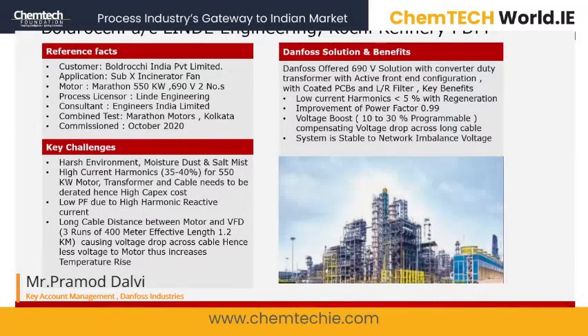We can program up to 30%. This will compensate the voltage drop across the cable. The motor will see the exact nameplate rated voltage, and there are no issues of lesser voltage and higher current and temperature rise. So this is one of the major advantages that active front-end drives can give for high power drives.